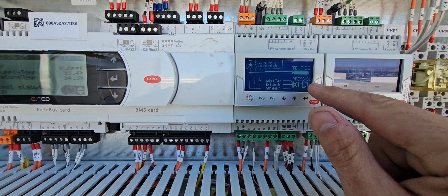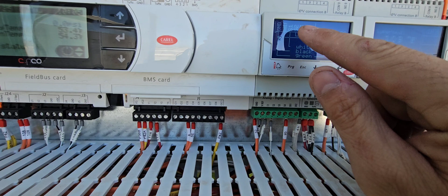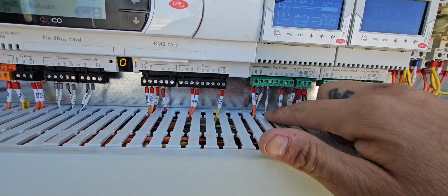So that's cool, and it also shows you your sensor and your transducer, which are going to be down here. So if you look, sensor is S2 and ground. We have S2 for sensor, and then white, black, green. We got white, black, and then our ground's gonna all be common somewhere else.